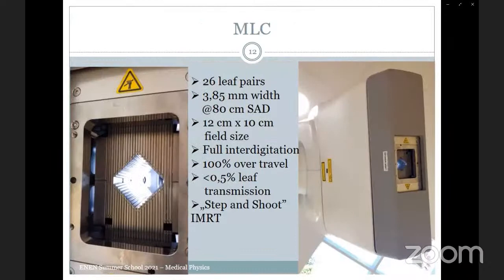With the multi-leaf collimator, as you can see on the image, you can create any type of field shapes with 26 leaf pairs, and each leaf pair has a 3.85 mm width at the 80 cm source axis distance, so it's very small leaves, and you have a maximum field size of 12 times 10 cm, and the MLC can do full interdigitation and 100% over travel. The radiation transmission through the leaves is below half percent, and with this the machine can deliver the so-called step and shoot intensity modulated radiotherapy.